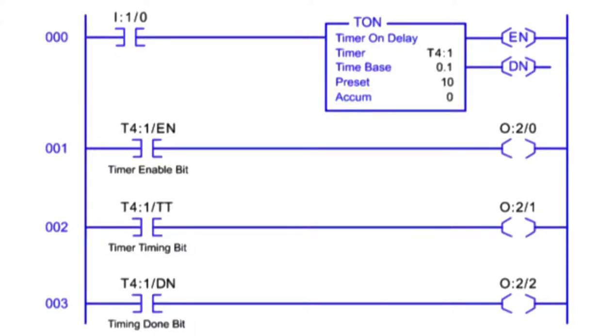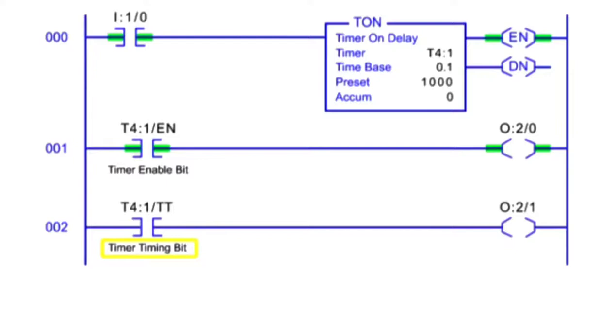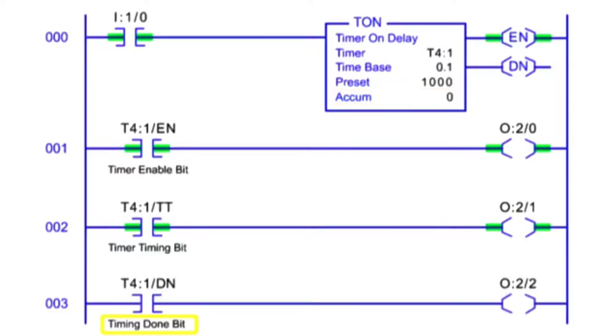For timer instructions, three control bits are available for programming use. The Timer Enable Bit status is true when the timer instruction is true. The Timer Timing Bit status is true when the timer is timing and the accumulated value is changing. The Timer Done Bit status is true when the accumulated value meets the preset value.